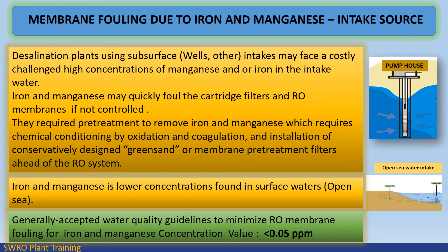Desalination plants using subsurface wells or other intakes may face a costly challenge of high concentrations of manganese and/or iron in the intake water. Iron and manganese may quickly foul the cartridge filters and RO membranes if not controlled, requiring pretreatment by oxidation, coagulation, and installation of conservatively designed greensand or membrane pretreatment filters ahead of the RO system. Iron and manganese in lower concentrations are found in surface waters. The generally accepted water quality guideline to minimize RO membrane fouling is an iron and manganese concentration of less than 0.05 ppm.